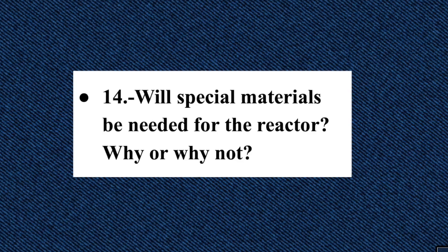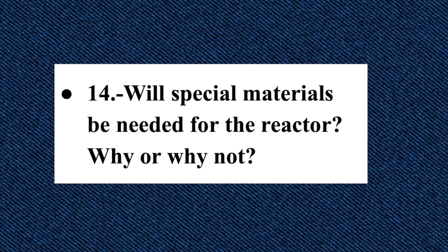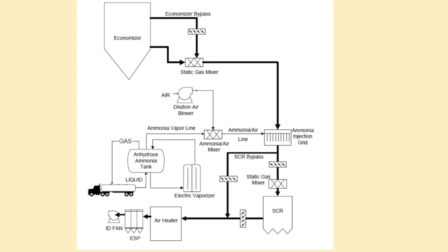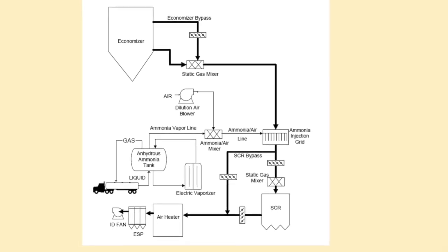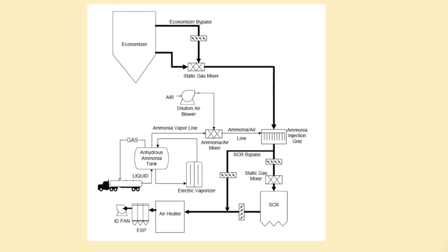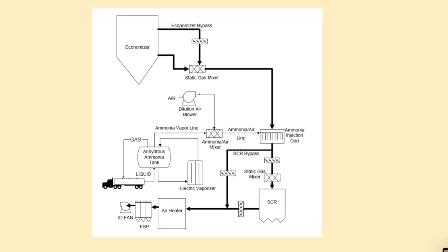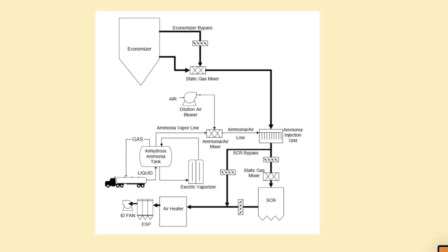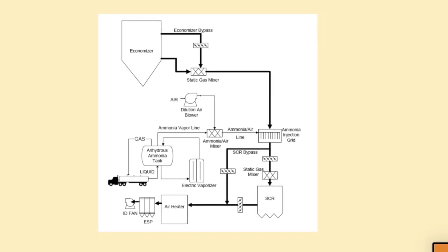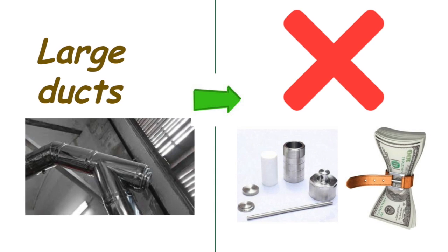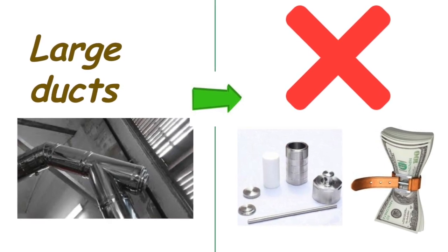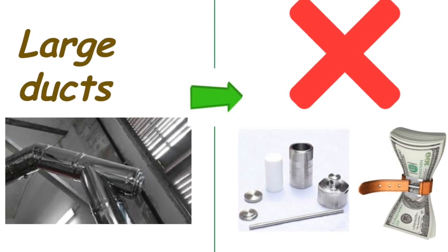Question fourteen: will special materials be needed for the reactor? It depends on the kind of reactor. There are two types: the full SCR and the in-duct SCR. Full SCR stores the catalyst in a separate reactor chamber, where combustion gas is conducted from the economizer to the reactor and then to the air heater entry. A separate reactor allows a large volume of catalyst to be installed in layers. In the in-duct SCR, the ducts are made larger to provide space for the catalyst. This kind of reactor saves duct, reactor chamber, and fan costs.